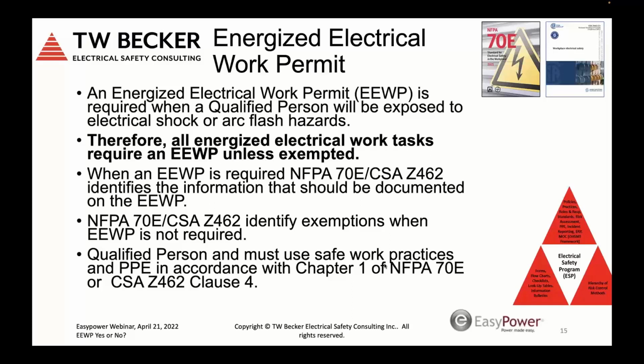So all energized work tasks would have the permit unless exempted. But the content in 70E, which is harmonized with Z462, says, wait a minute, there's justification for energized electrical work, and the permit's going to be exempted for some of those work tasks because we can't complete them due to equipment design. So the starting point of the permit was you need it for everything, but there was some recognition that due to justification, the permit's not required. It's moot.